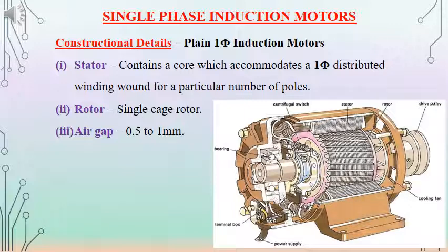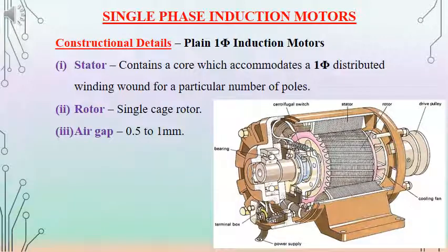We will consider the construction details of single phase induction motor. We have the stator, rotor, and air gap. On the stator side, the motor has a core accommodating a single phase distributed winding, wound for a particular number of poles depending on the speed required. On the rotor side, it is a squirrel cage type as in three phase induction motors. The air gap between rotor and stator is of the order of 0.5 to 1 millimeter.